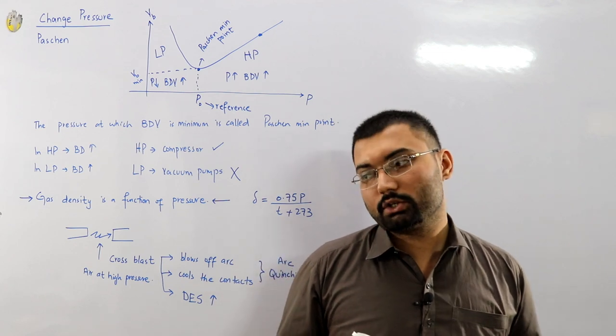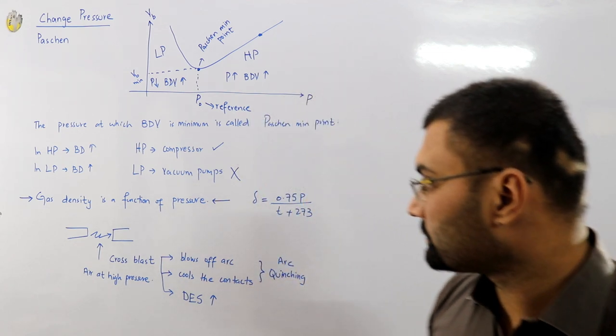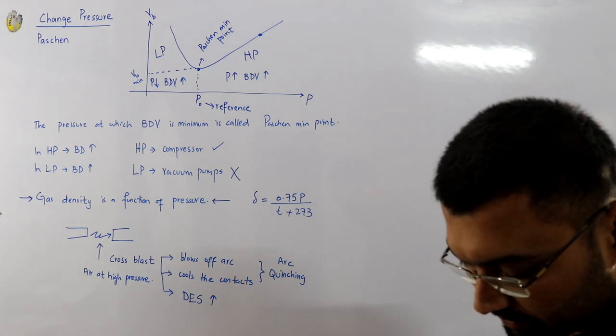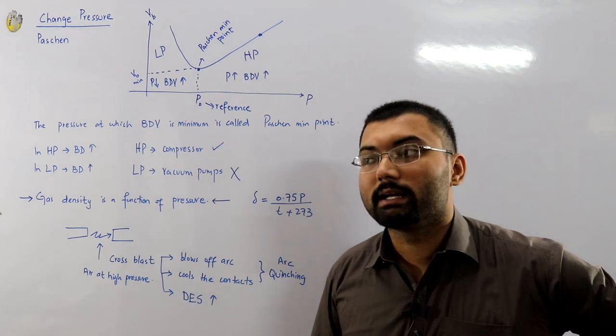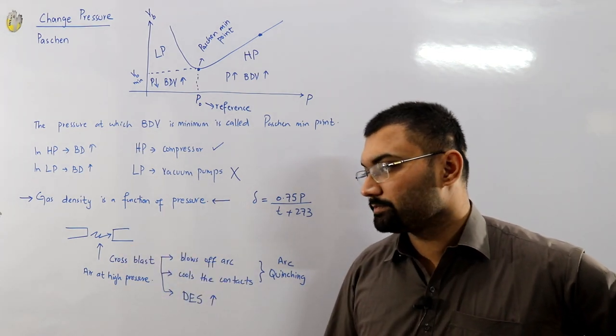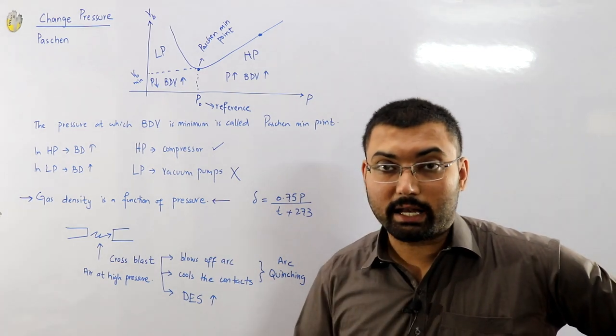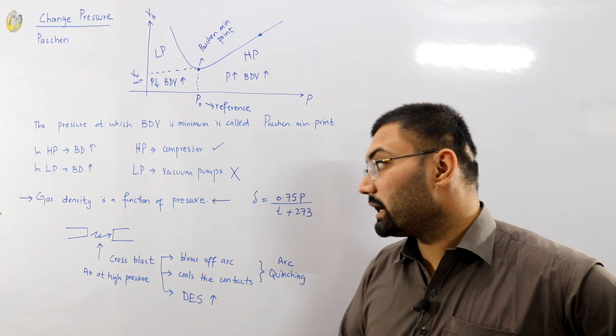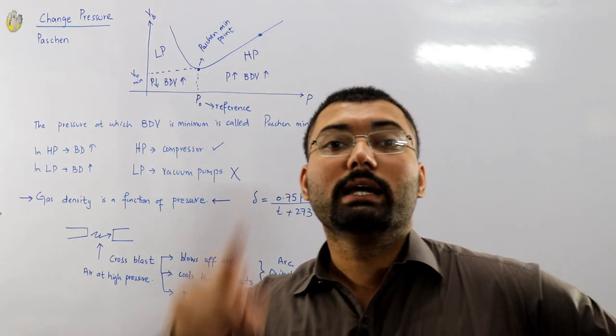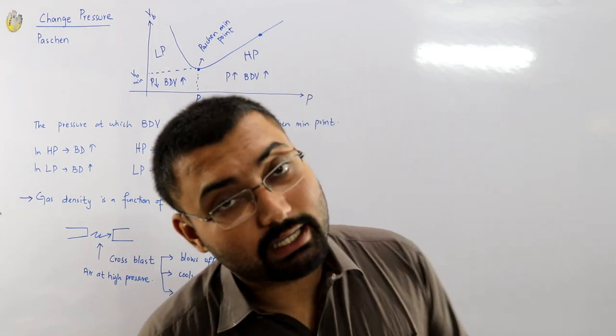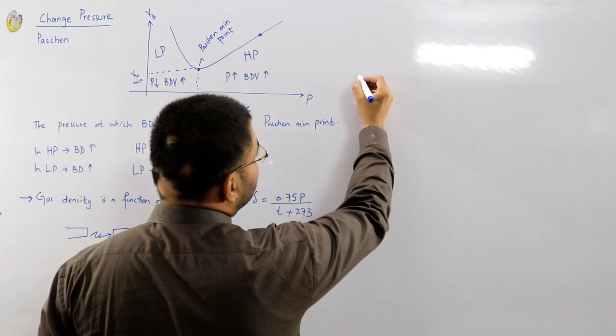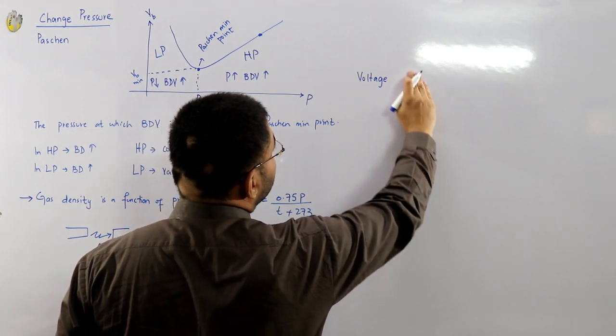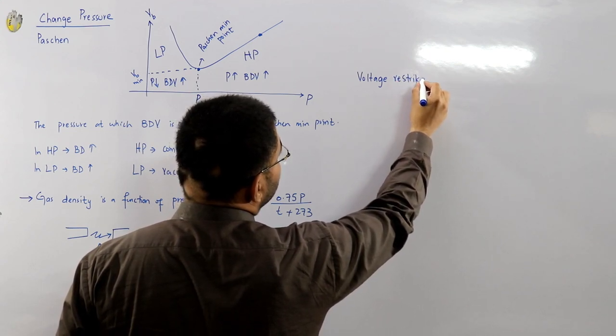However, there is a restriking voltage. Just as a doctor gives you an antibiotic for illness — you have to complete the full course or the bacteria attacks again — similarly here the voltage will restrike, and that restrike is even more dangerous. It works like a capacitor building up a voltage of twice the maximum value, so the restrike voltage is much more dangerous than the original arc.